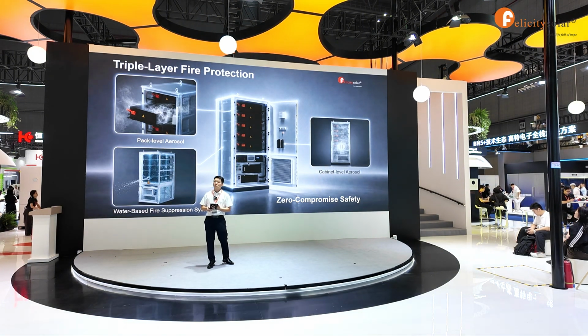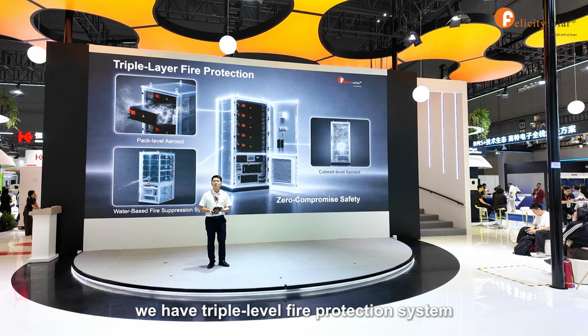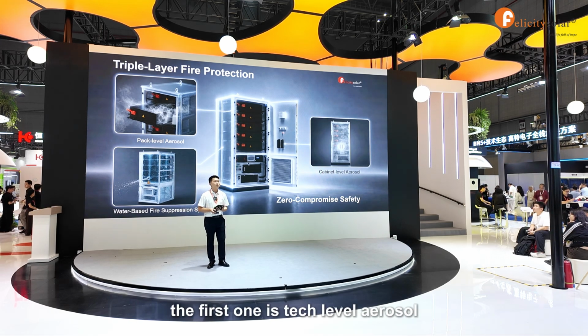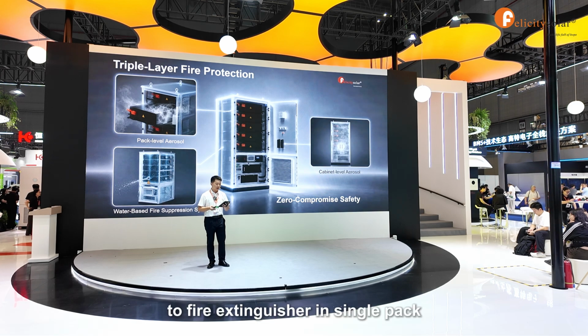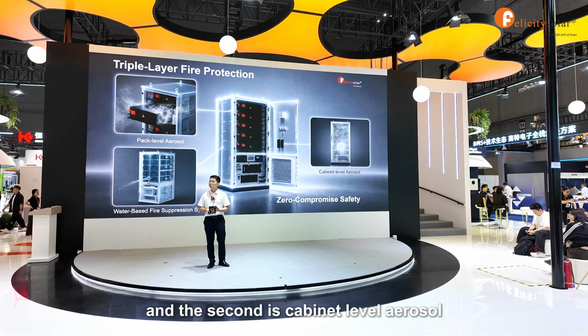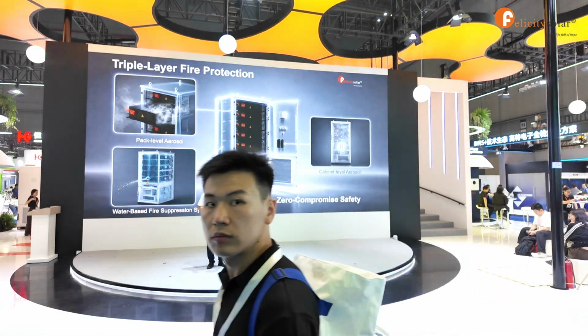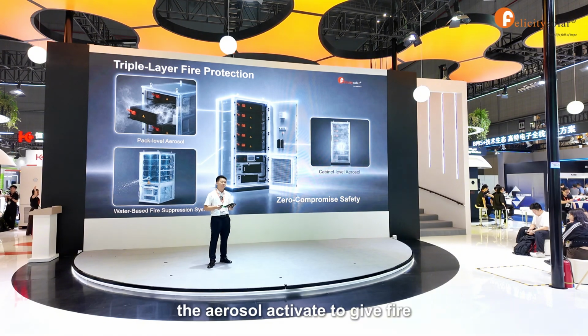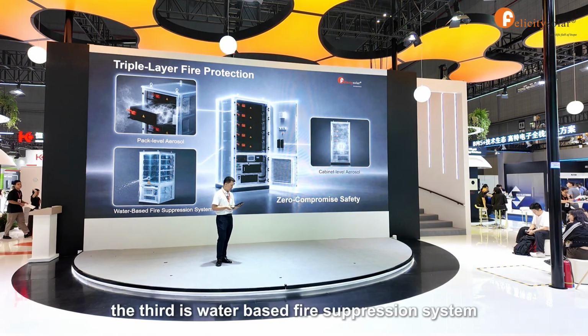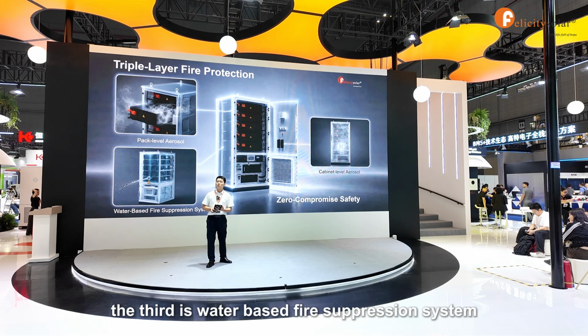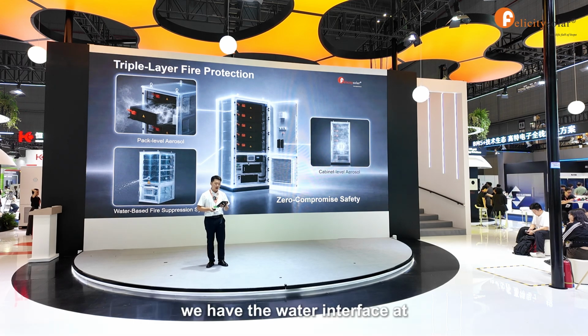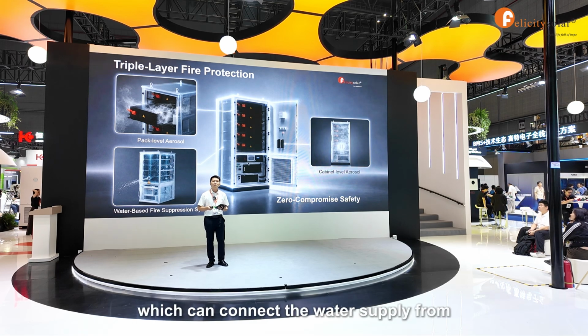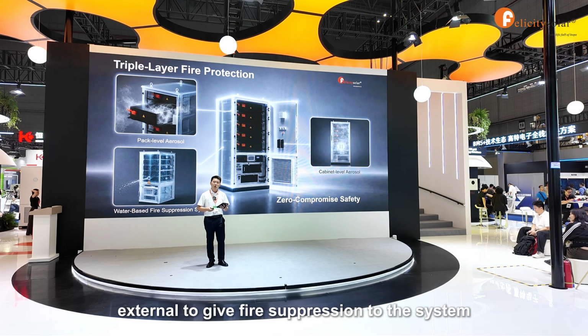About safety, we have triple layer fire protection. The first one is pack level aerosol to extinguish fire in a single pack. And the second is cabinet level aerosol. When a fire happens in the cabinet, the aerosol activates to extinguish the fire in the cabinet. The third is a water-based fire suppression system. We have the water interface at the back side of the cabinet, which can connect the water supply from external to give fire suppression to the system.